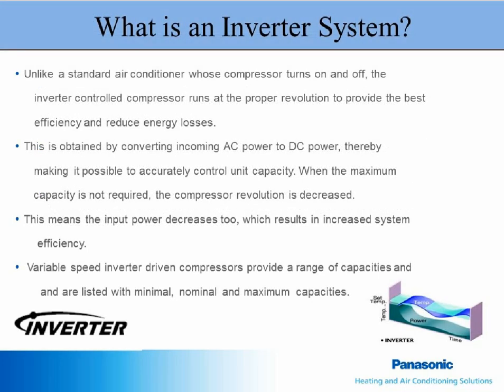All Panasonic systems use inverter compressors. What is an inverter system? Basically, it is a system with a variable speed compressor and multi or variable speed fan and blower motors. This, along with multiple thermistors, an electronic expansion valve, and intelligent circuitry, means Panasonic mini splits are able to provide excellent comfort and energy efficiency. The compressor capacities will vary from approximately 20 to slightly over 100% of its rated capacity. All this means you get the capacity you need, not more or less.